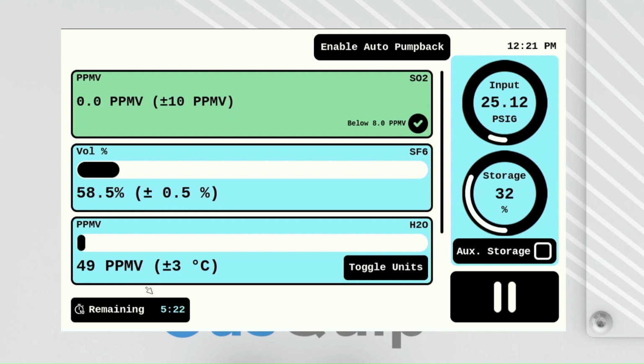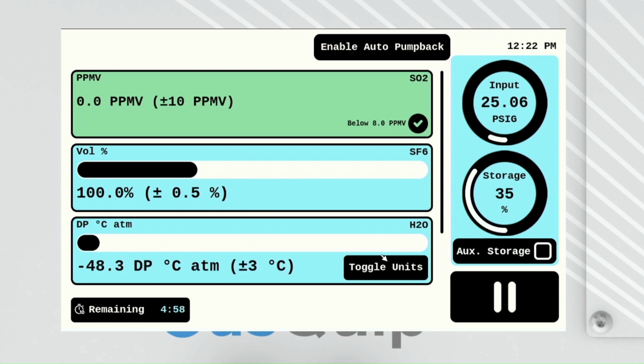As our SF6 and H2O tests run, we can point out here the live readings. So we have 92.3%, which should continue to rise as we test this pure bottle of gas. The accuracy is listed as plus or minus 0.5%. That comes directly from the sensor. And then of course for our H2O sensor, we have a reading of 49 ppmv, which again can be toggled to a different unit by hitting this button.